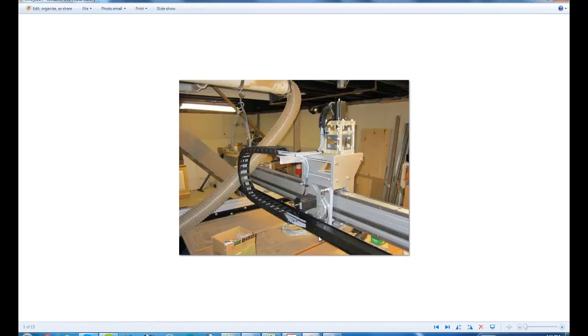This is actually wire duct right here, and it worked out to be a much better solution than leaving the free leads and using, say, XLR connectors, which I used for a long time. I realized I didn't need any kind of quick disconnect - these motors just don't get changed out, and you don't do anything with the wires. So adding an extra connection at the motor and then at the enclosure - a lot of people, and I certainly did for a long time, put XLR or other motor connectors at the panel. There's really no need for that.